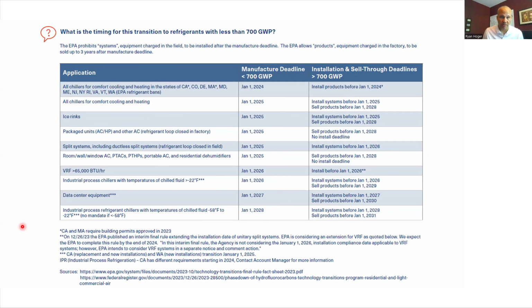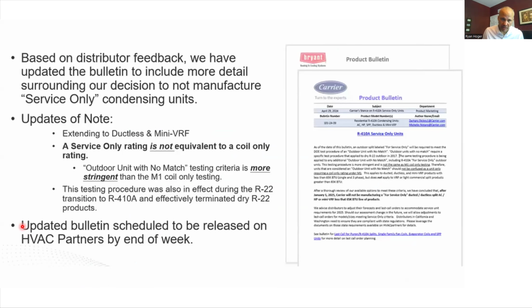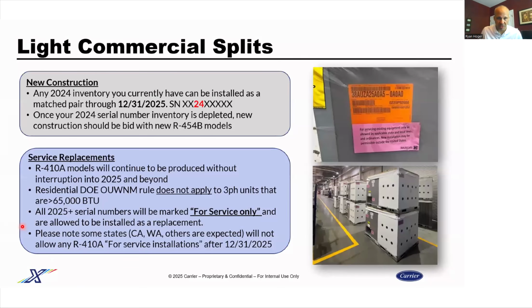These dates only apply to the piece of equipment that has the compressor physically in it. But they cannot produce the condensing unit. However, there's also a loophole for that. They can continue producing R-410A condensing units residentially and commercially indefinitely if they label them as service only, put a tag on there, a big pink sticker, whatever, that says this is for service only replacement, and you cannot install this as a new piece of equipment.